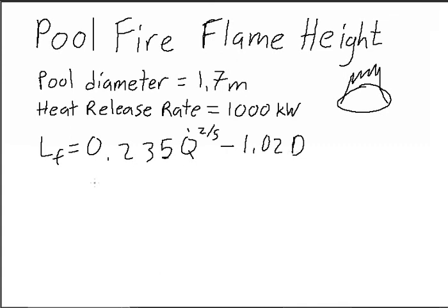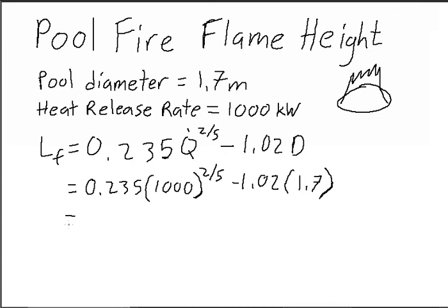where Q dot is your heat release rate. So, we can work this out, pretty straightforward, 0.235 times 1,000 to the two-fifths power, minus 1.02 times 1.7, and that's equal to 1.99 meters.